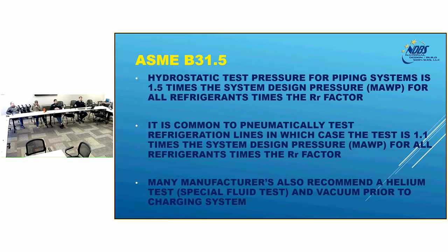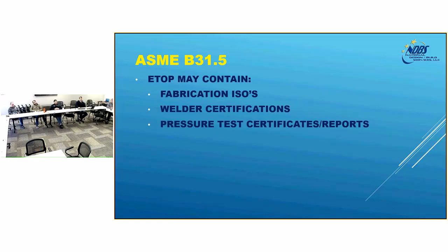So I'm thinking of your VRF systems, variable refrigerant systems. I've never had the pleasure of doing a helium test, but it's another ASME B31.5 test method that can be used in conjunction with pneumatic testing. Pretty much the same story on ETOP.